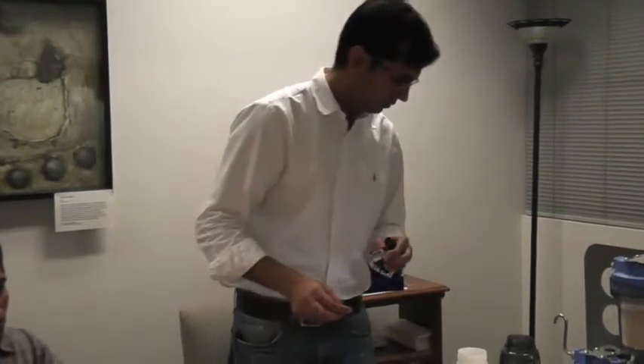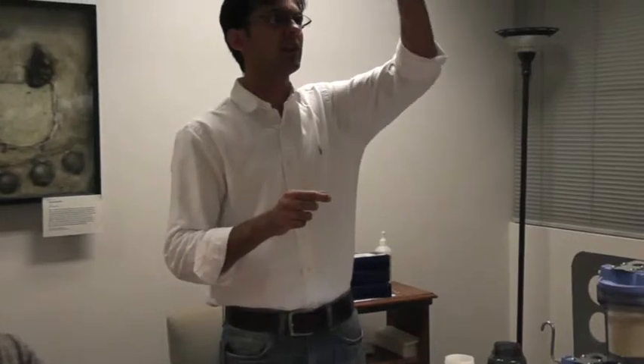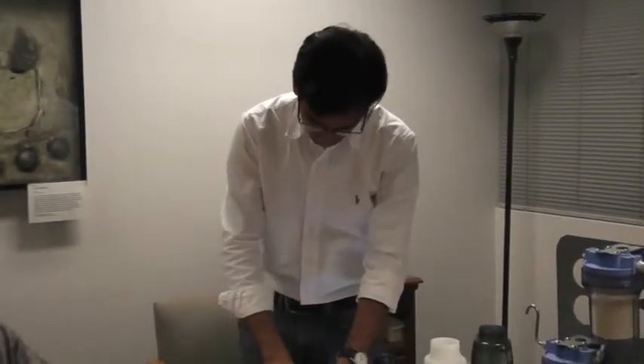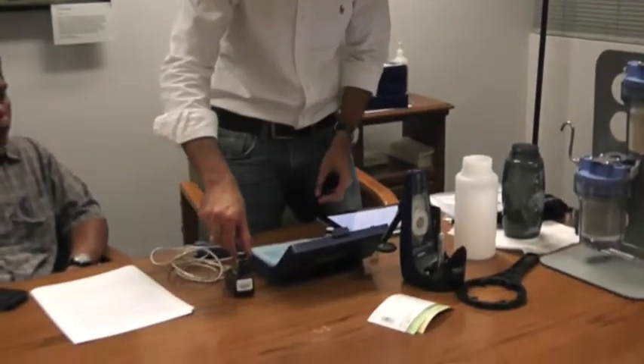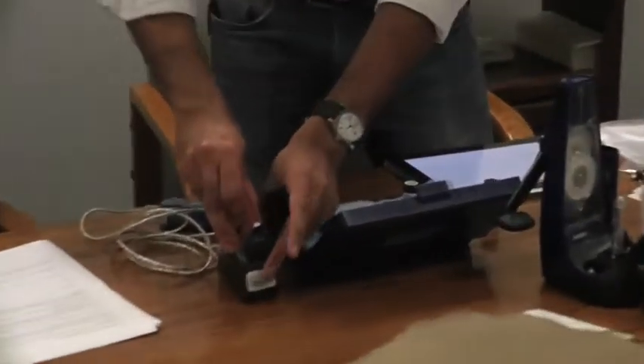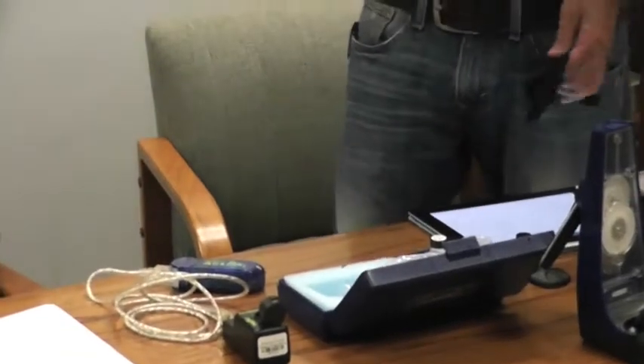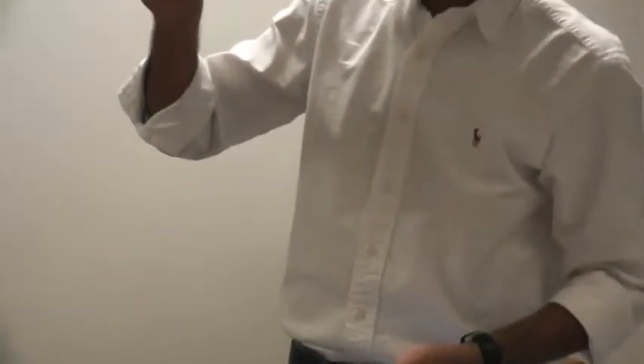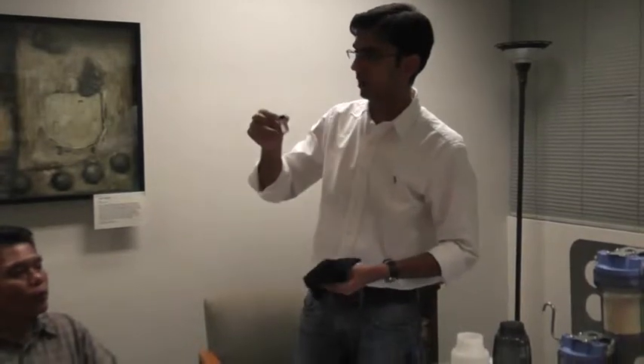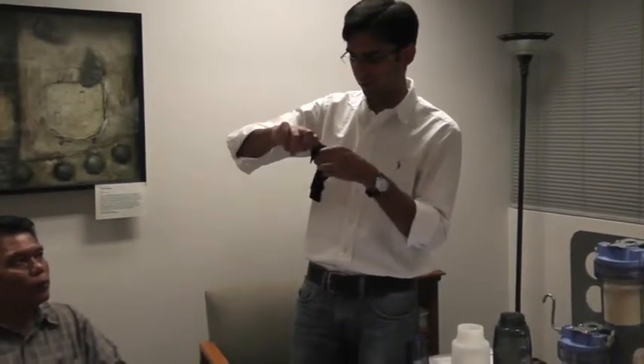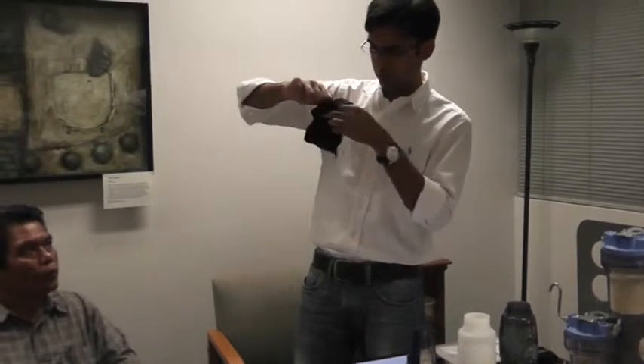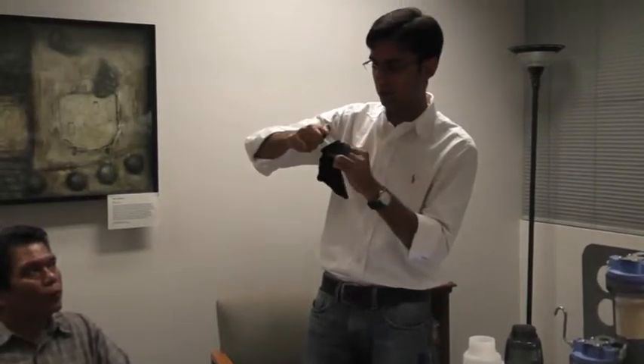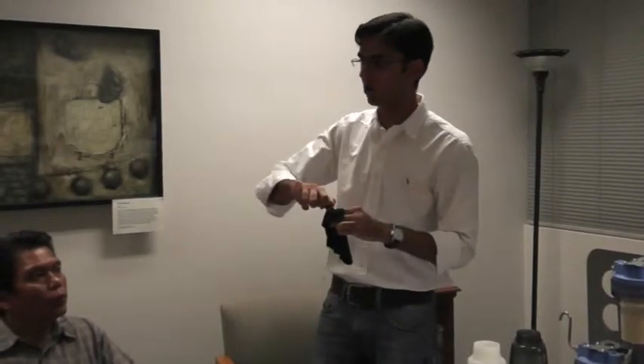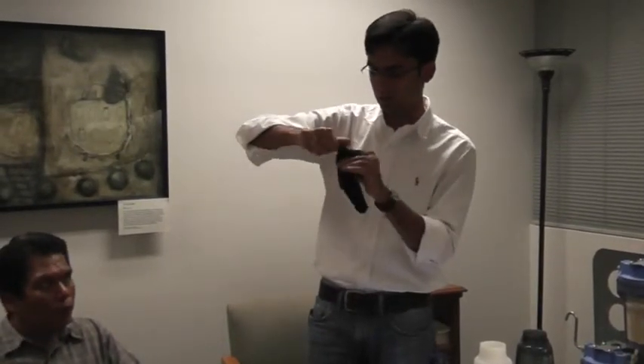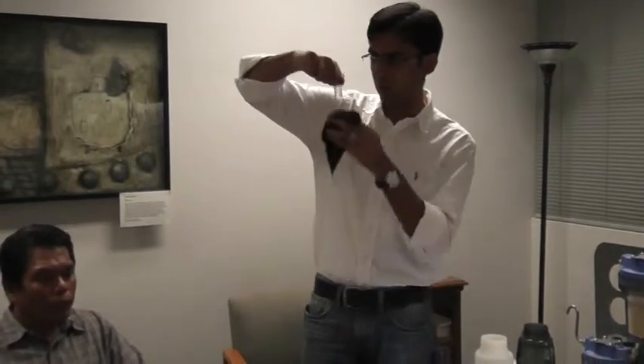Okay, so that's the clean one. Yeah, you can see it. Okay, so let's start with 100 NTU. So you insert the vial. Actually, the first step I forgot. Sorry. You would want to make sure that there are no fingerprints on the outside of the vial or any water droplets. So you just clean it with a cloth to make sure that the outside surface is clean, because again the concept of turbidity is bouncing light into the water and seeing how much reflection it gets. So you don't want external distortions on the vial.